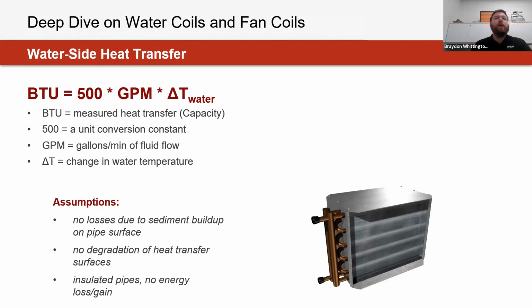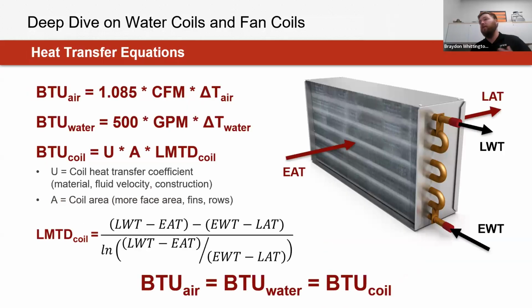And one key formula I would say that a lot of people don't really take into account there too is the BTUs, or the capacity of the coil itself. The reality is that there are other coefficients that come into play when evaluating the heat transfer at the coil level, such as the material, which we're going to get into a little bit, rows, fin density, and also circuitry and utilized face area, but also different coefficients based off of what material is used and how that coil is going to be constructed.